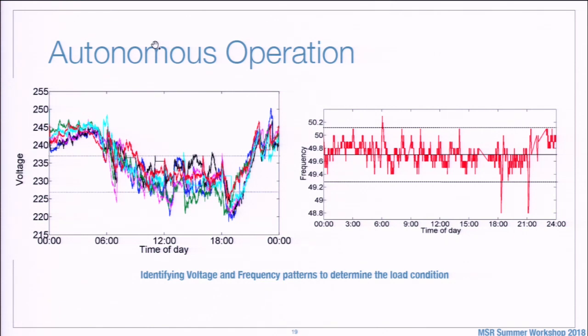In the morning, or overnight, the voltage is high since these are off-peak times—above 230 volts, though nominal voltage is expected around 230; at night we typically see 245 to 250 volts. In the evening peak times, around 6 to 9, there's a significant drop to around 220 volts. This was in Bangalore, where the local transformer was very close to my house.